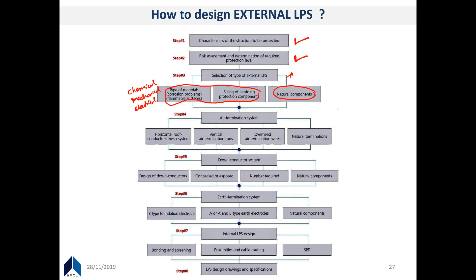If we have a steel roof with adequate thickness, and if you have proper bonding to the down conductors, and proper earthing of them, then you can consider this as a natural component. This roof is a natural component. You can consider certain pipes with adequate thickness if they are not being used for other services, but obviously you have pipes for a particular purpose. So if you are using pipes for a service, it's a matter of fact, and it's also mentioned in the standard, that you cannot use those pipes considering the service it is being employed for at the moment.